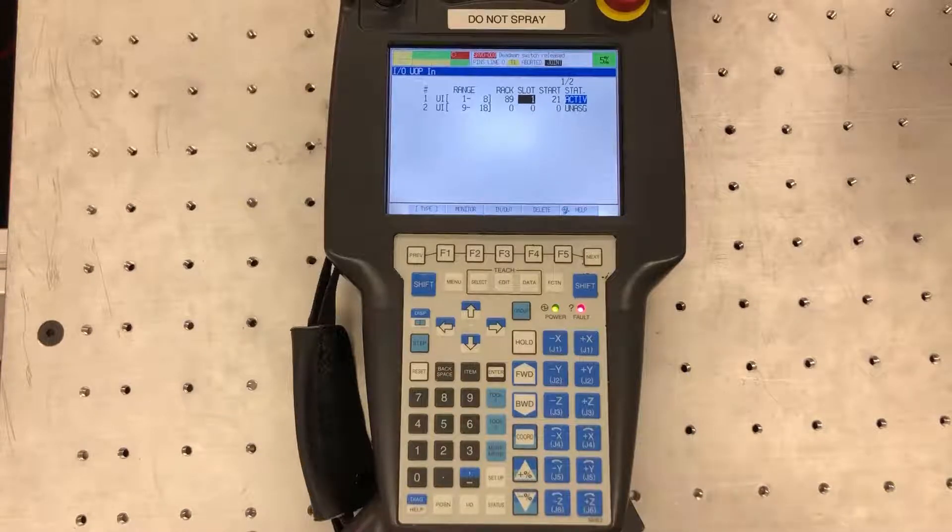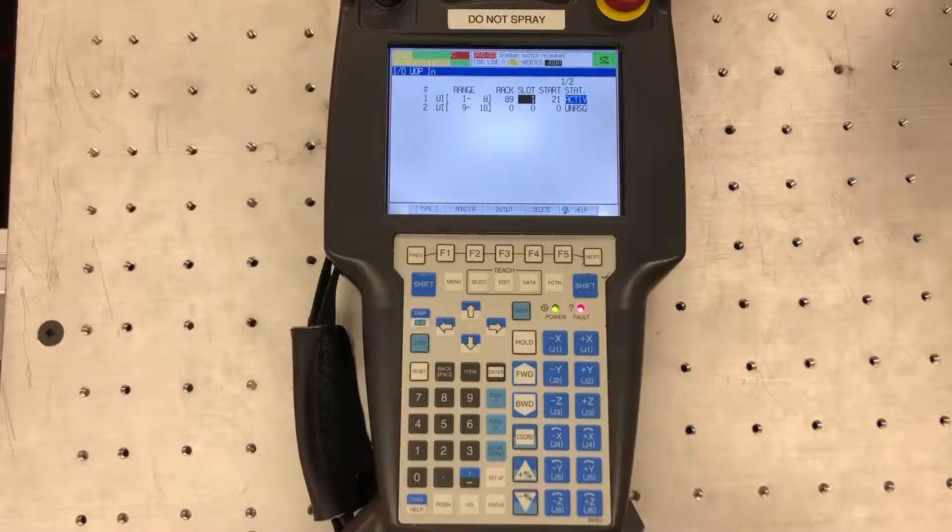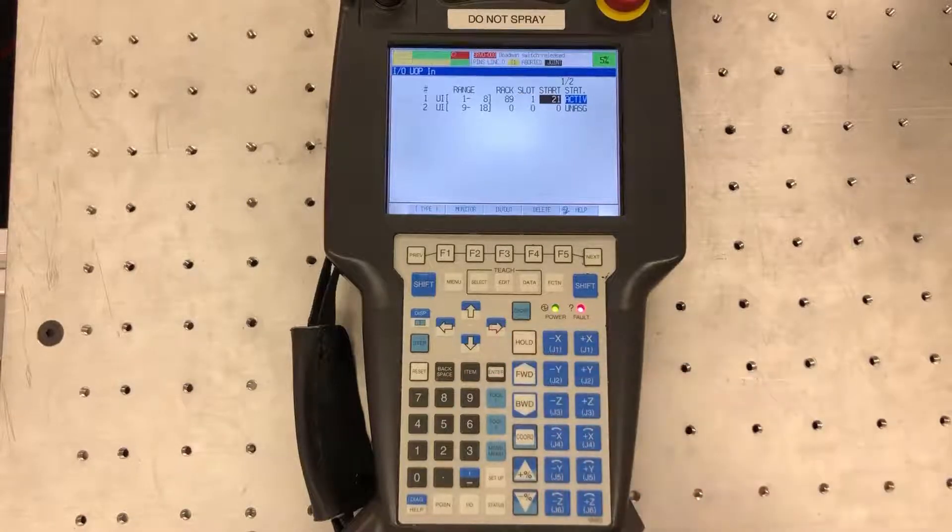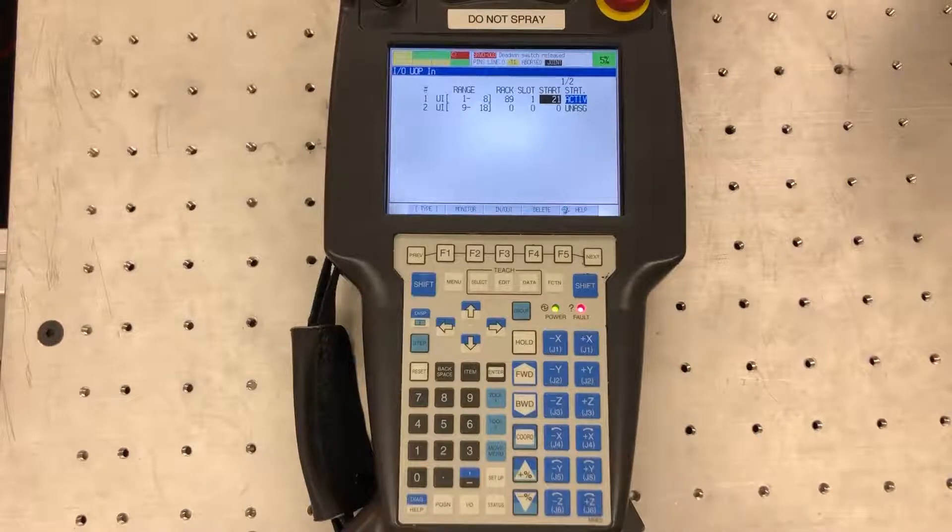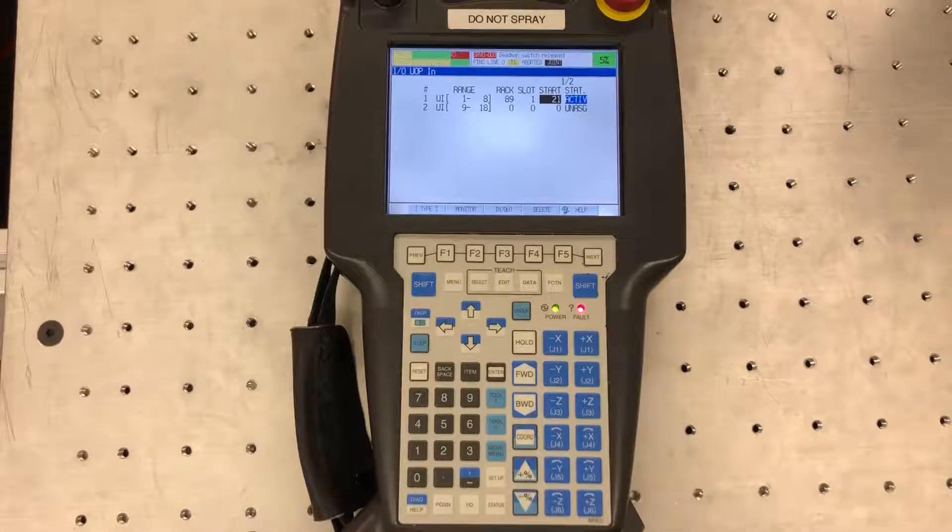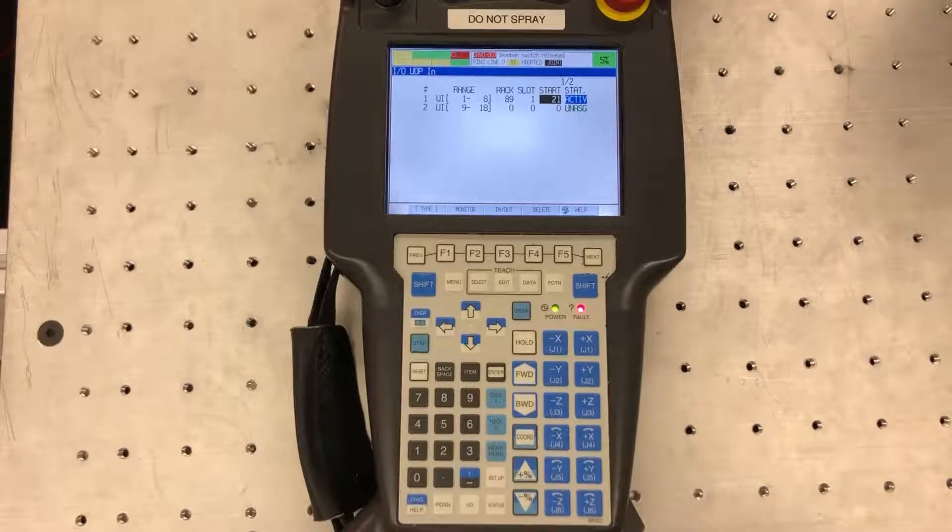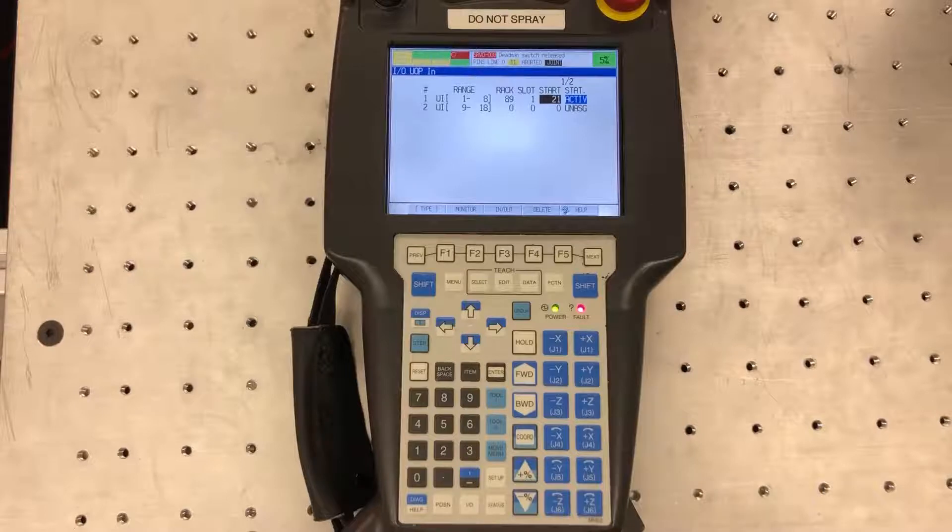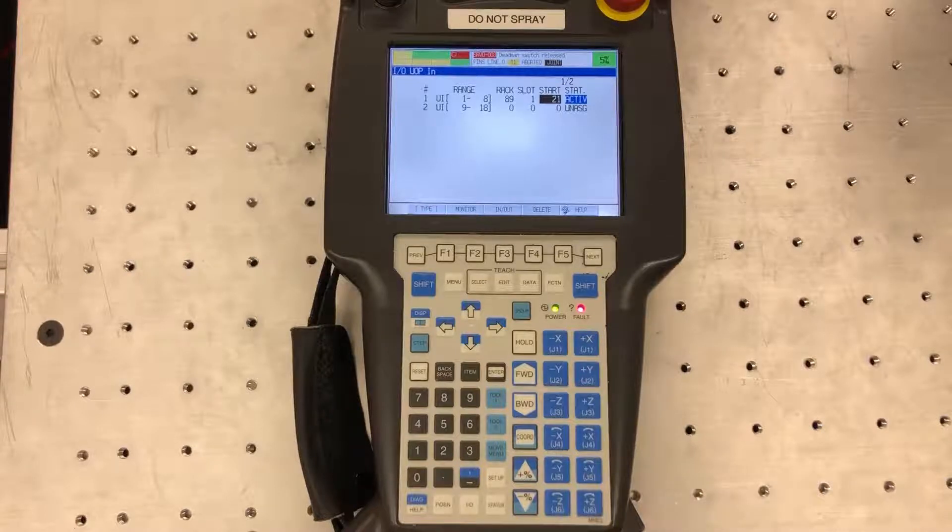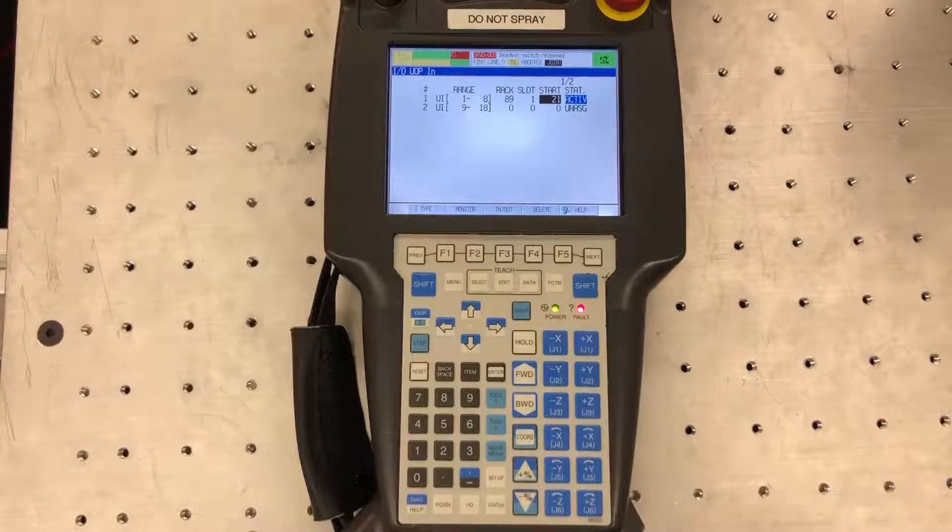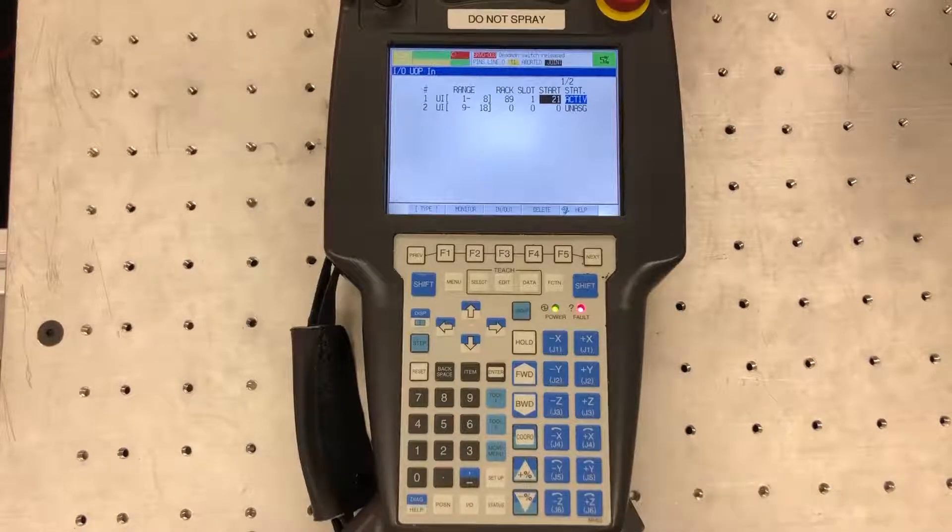Next you're going to go over to your start instance. So this is going to correlate more to the assembly instances you'll find on the PLC side. You can think about it as there's a certain range of bits this is going to map to. So the first bit of 8 on your range of 1 through 8 bits, that first bit is going to map to your 21st on the other side.